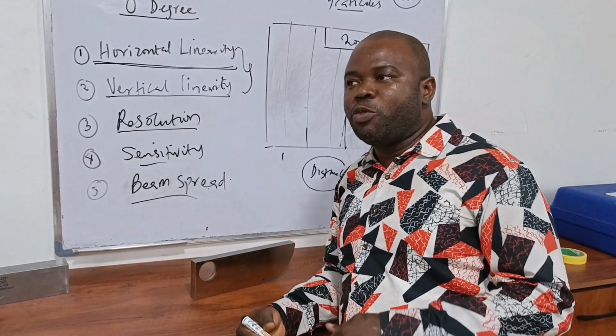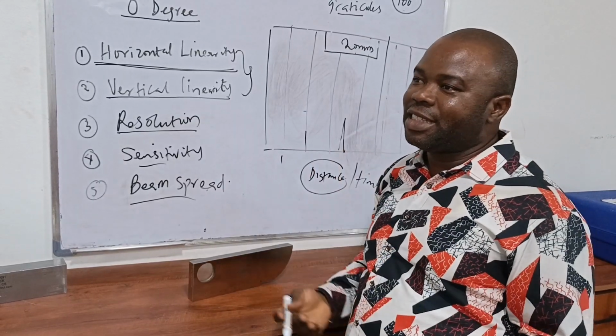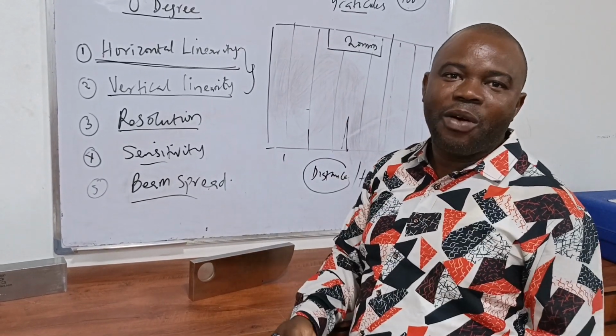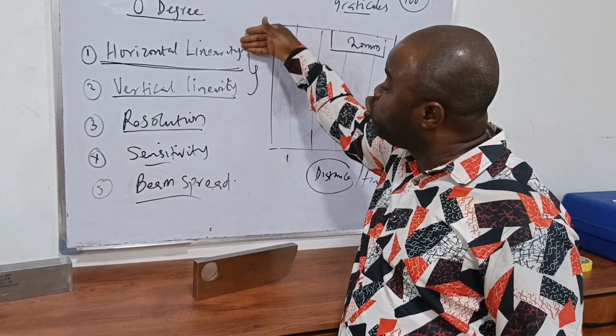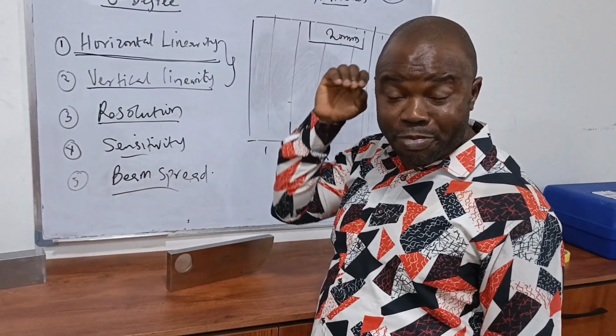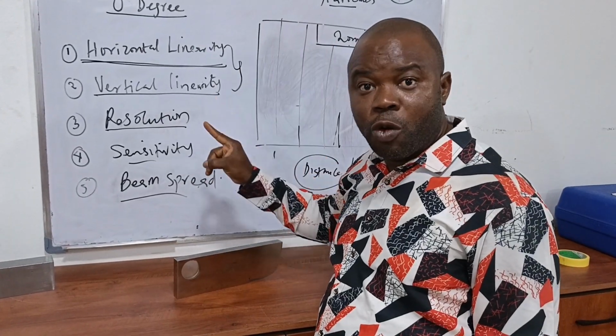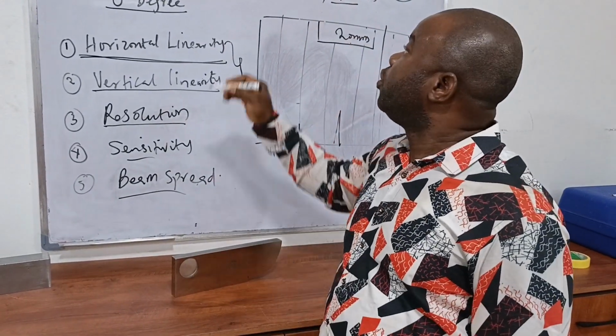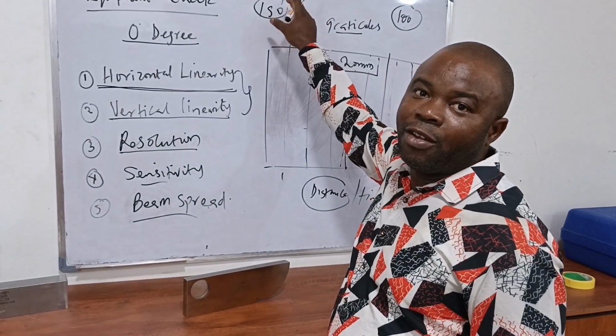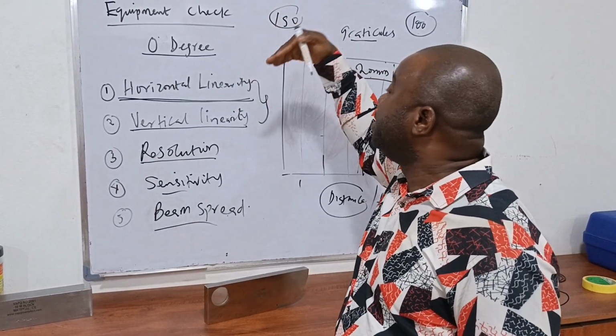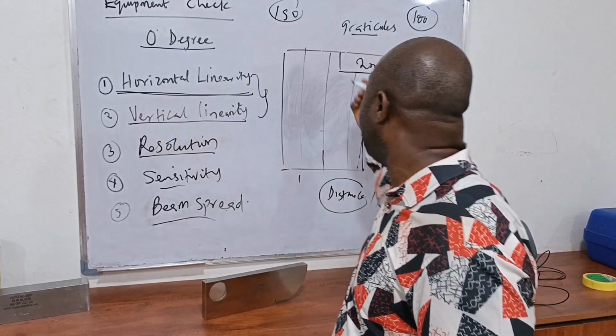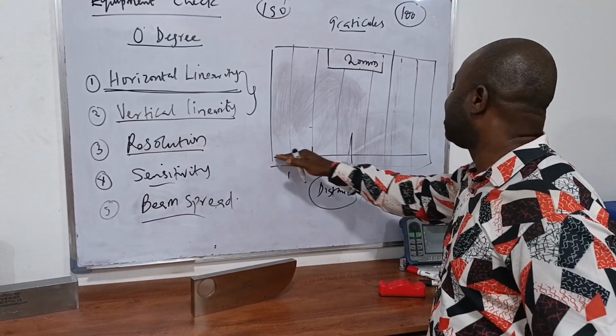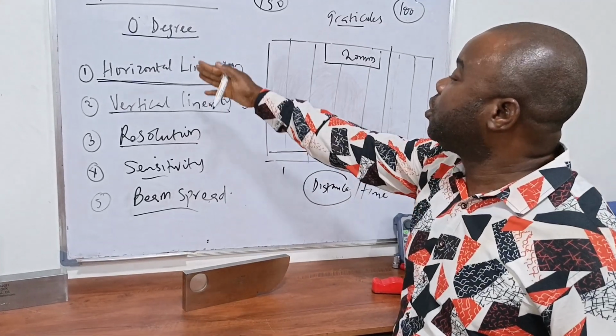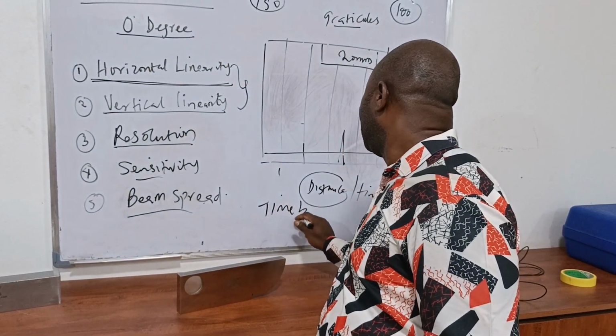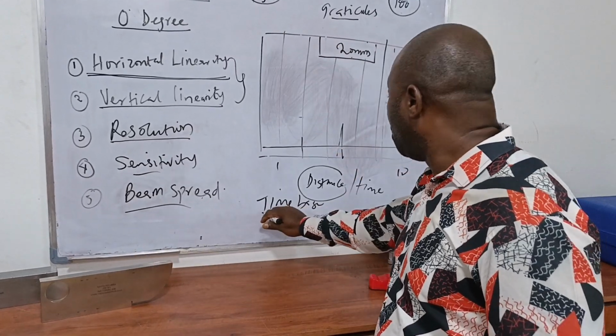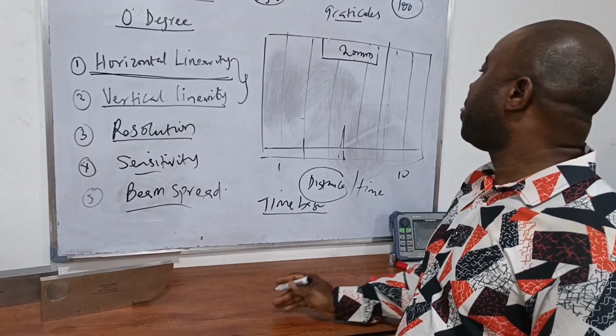If you look at your UT procedure, you might be told to perform horizontal linearity once a week, or every 8 hours, or at the beginning of the shift. How often you do your horizontal linearity is basically up to your procedure. However, if there is no procedure, you can check your ISO standard for UT. When you talk about equipment check, they will give you the frequency of checking for your horizontal linearity. So your horizontal linearity is for your distance. Or another name for horizontal linearity is what we call our time-based linearity. So that is the horizontal linearity.